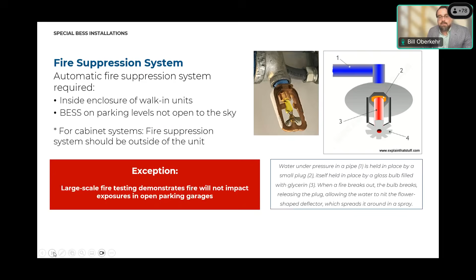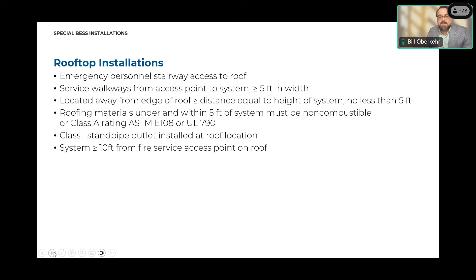Rooftop installations should have access from the inside of the building for first responders in the event of an emergency. The roof should also have a standpipe that the fire service can use to put water on the fire if that is necessary for that type of equipment. The energy storage system cannot be within 10 feet of that rooftop access that is also required. Next slide, please. Last one before we move on to the residential code, which I will also get through very quickly.